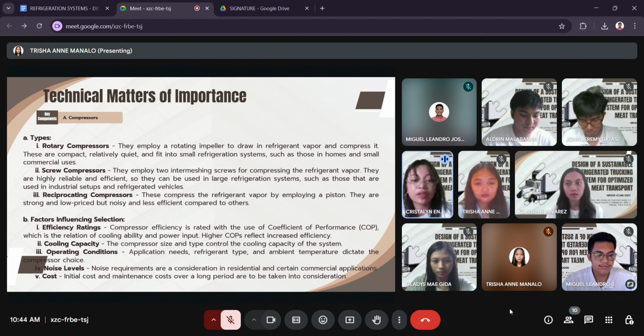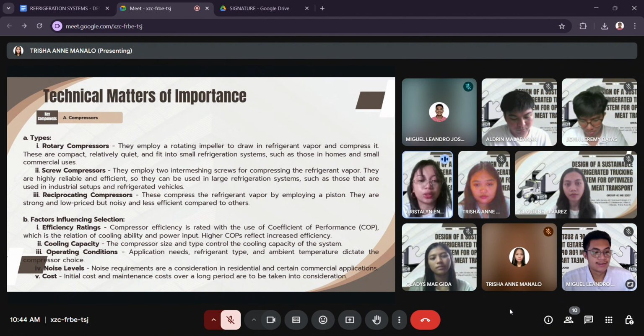Efficiency ratings: compressor efficiency is rated with the use of coefficient of performance, or COP, which is the relation of cooling ability and power input. High COPs reflect increased efficiency. For cooling capacity, the compressor size and type control the cooling capacity of the system. While in operating condition, application needs, refrigerant type, and ambient temperature dictate the compressor choice. Noise level requirements are a consideration in residential and certain commercial applications. Lastly, we have cost. Initial cost and maintenance cost over a long period are to be taken into consideration.